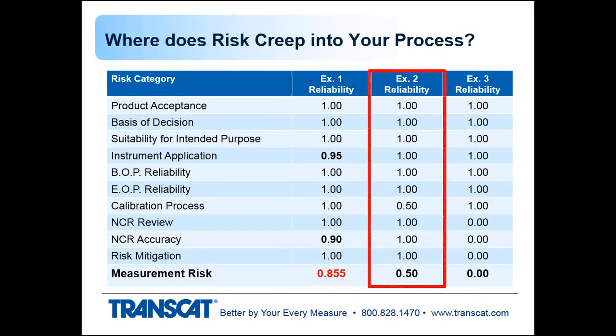In the next example, all values have a value of 1 except for the calibration process, where half of the calibration was missed. A real example of this that I've seen in my experience is a thermocouple-based device, a temperature reading device, where there were 2 channels on the instrument and only 1 channel was calibrated. Therefore, half of the instrument was traceable, half of the instrument was not. When we took a look at where it was used in the manufacturing process, indeed both channels were being used and relied upon. So that got a 50%, which took the entire rating down to 50% measurement risk.